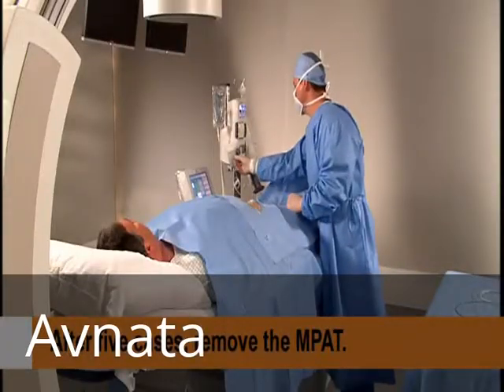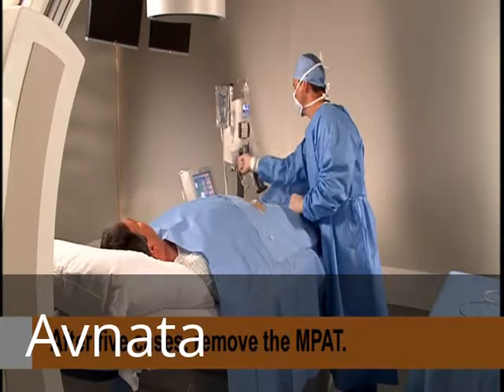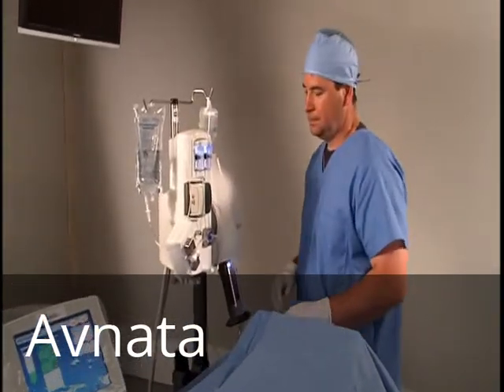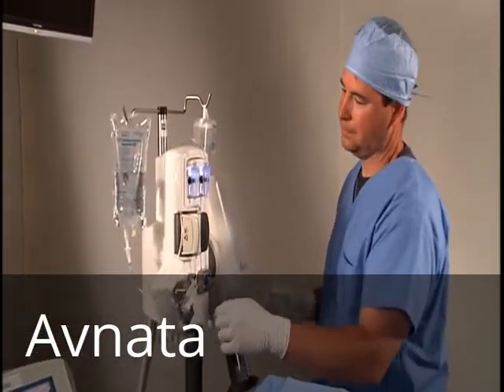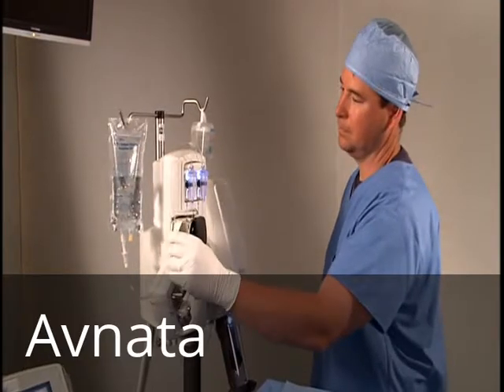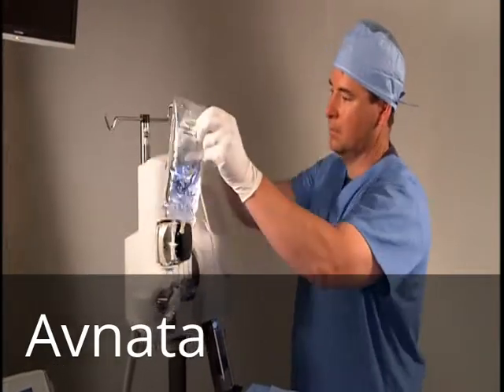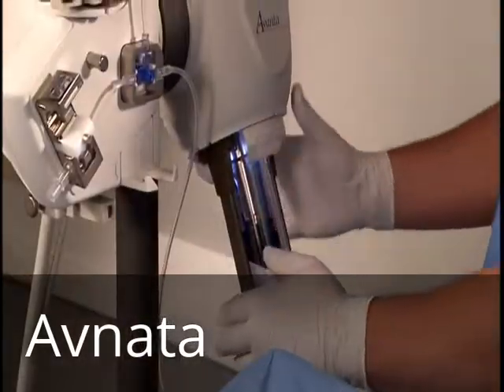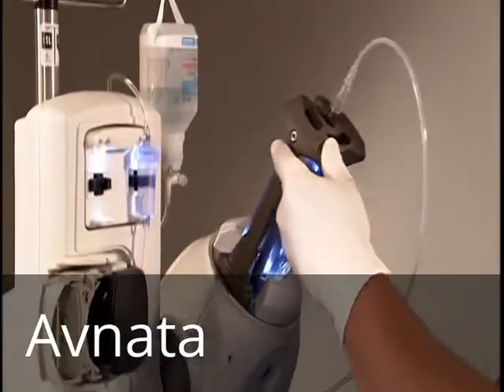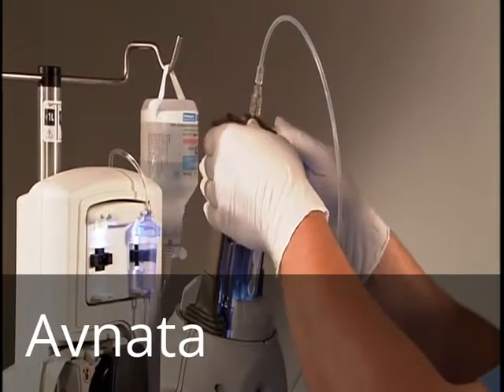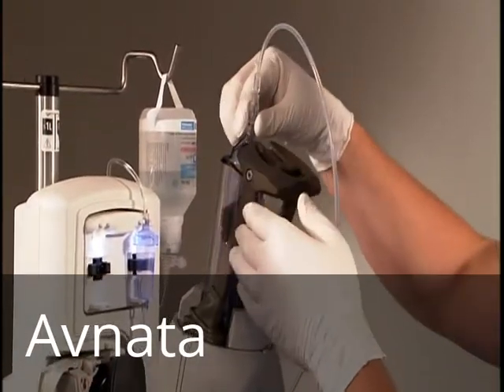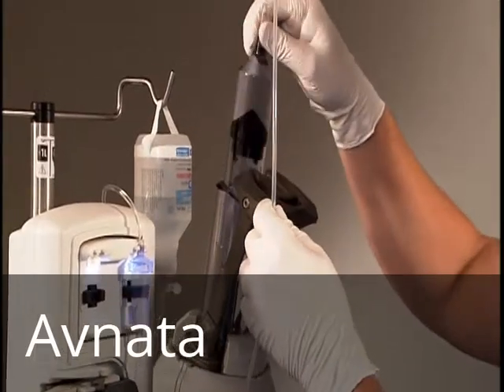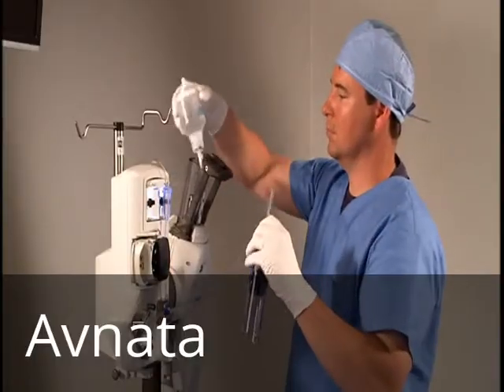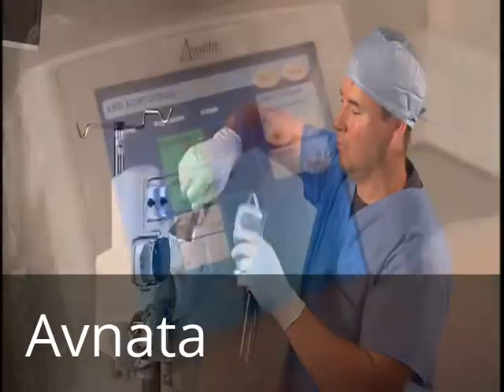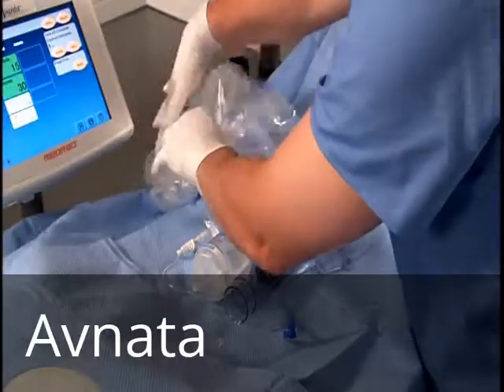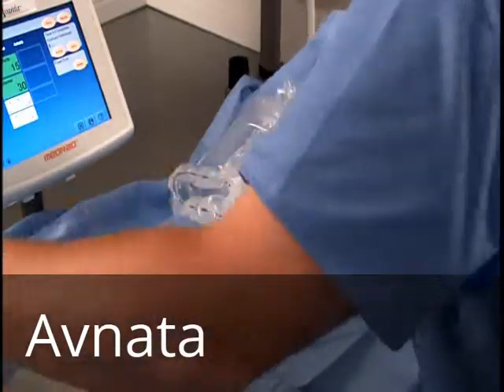After 5 cases, remove the multi-patient disposable set. To replace the multi-patient disposable set, open the gross air detector doors and the peristaltic pump door. Remove the saline tubing and bag. Next, remove the multi-patient contrast tubing set. Release the drop front arm and remove the syringe. Simply turn the syringe 1/4 turn clockwise to remove it from the piston at any position while it is still attached to the MPAT disposable tubing. The disposables have been designed to minimize contrast spillage during removal.